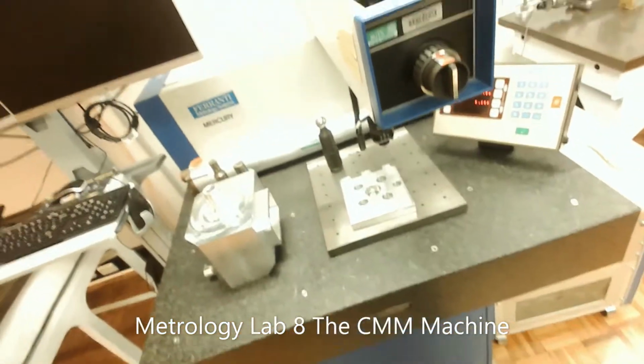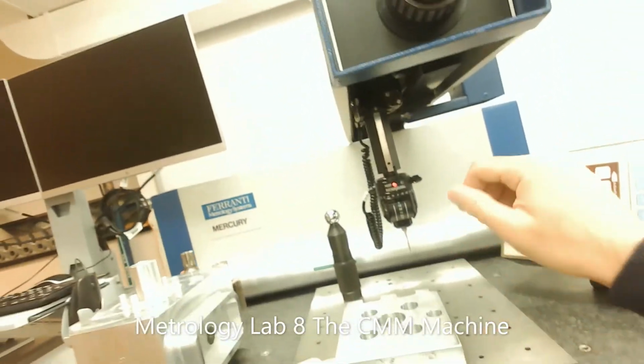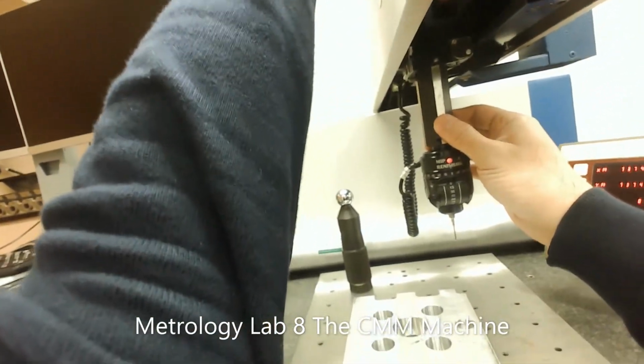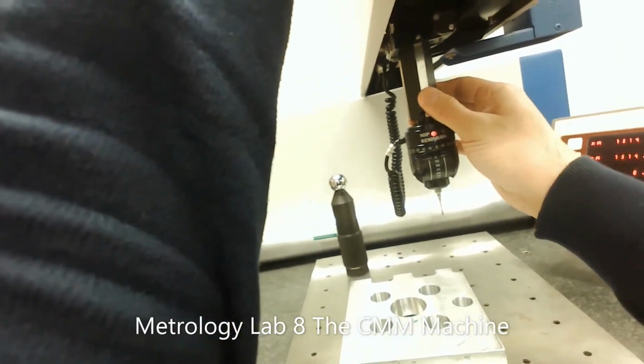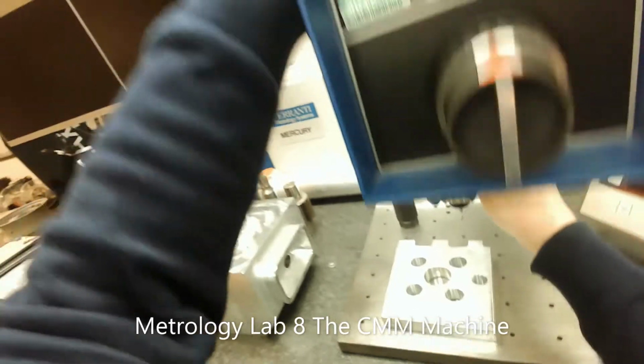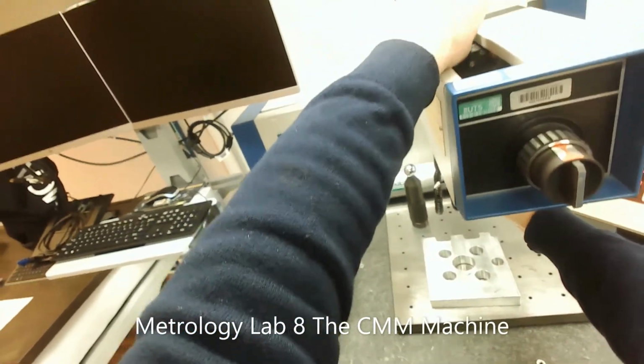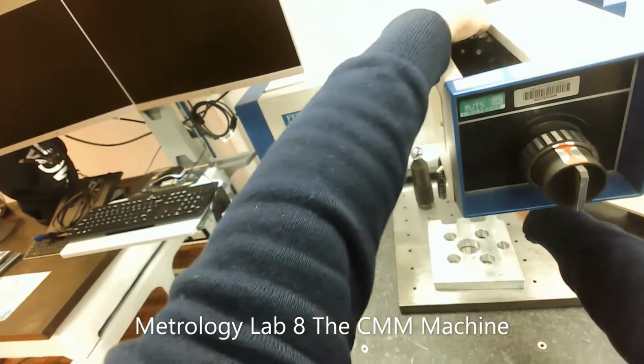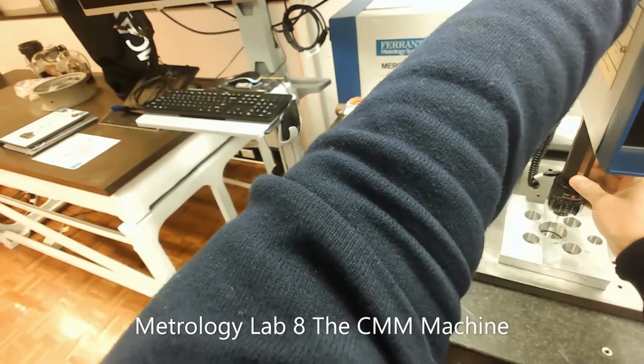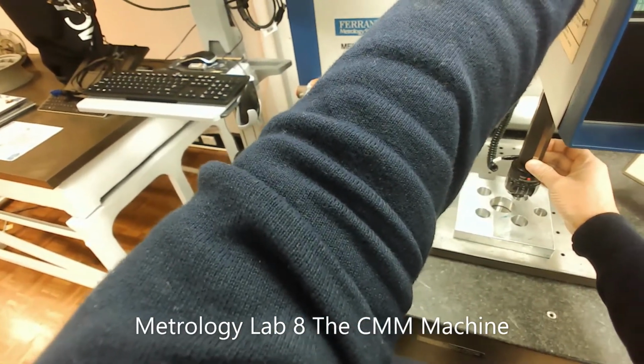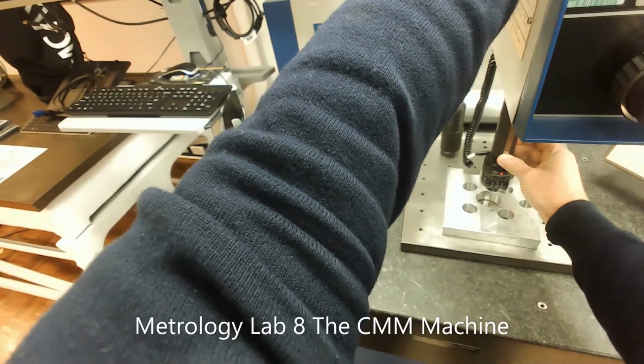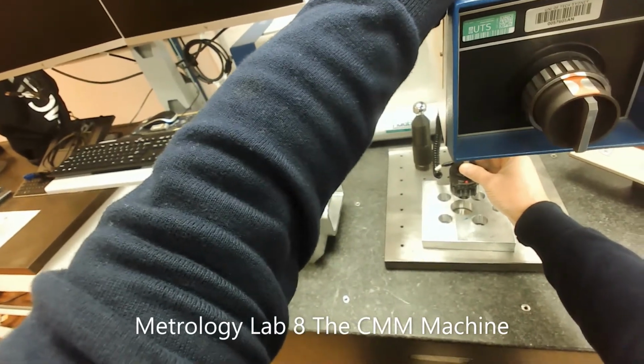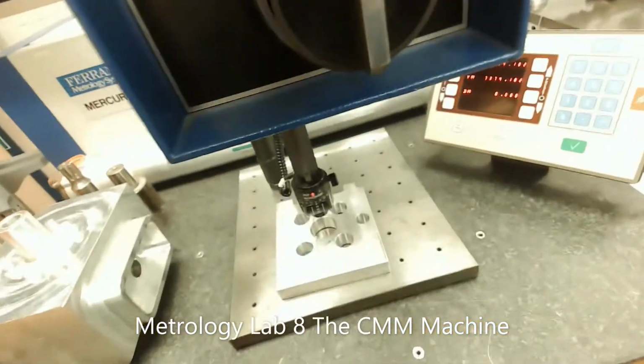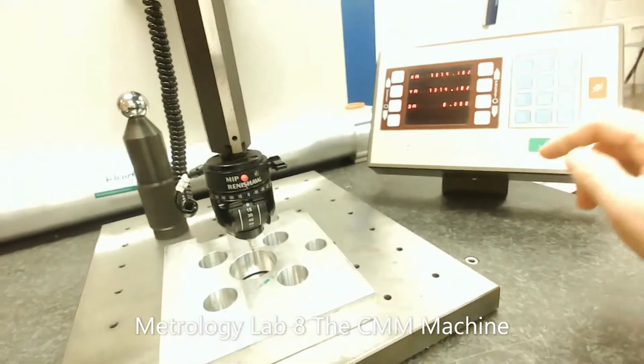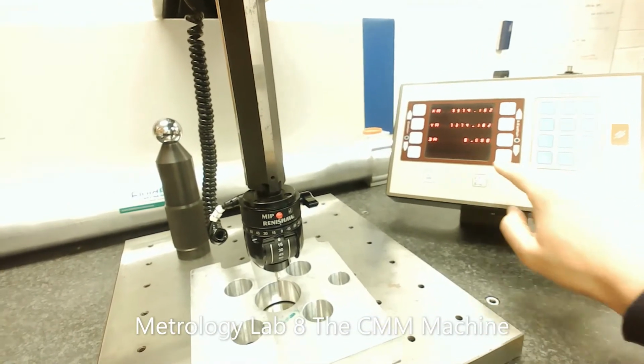Now what I need to do is take the probe down, and this approach is actually quite tricky because this probe is quite heavy, and any wrong movement can drop it and break the probe. Actually, in my time at UTS, I broke the probe 3 times. This can happen by releasing this lever down here and then trying to take the probe just below the surface side. So just checking that. Now, yes, it's touching the thing. I'll take it a little bit more. Yep, now it's fixed. Okay, now I'm going to start the measurement process again. So again, the process is done by pressing the measurement.